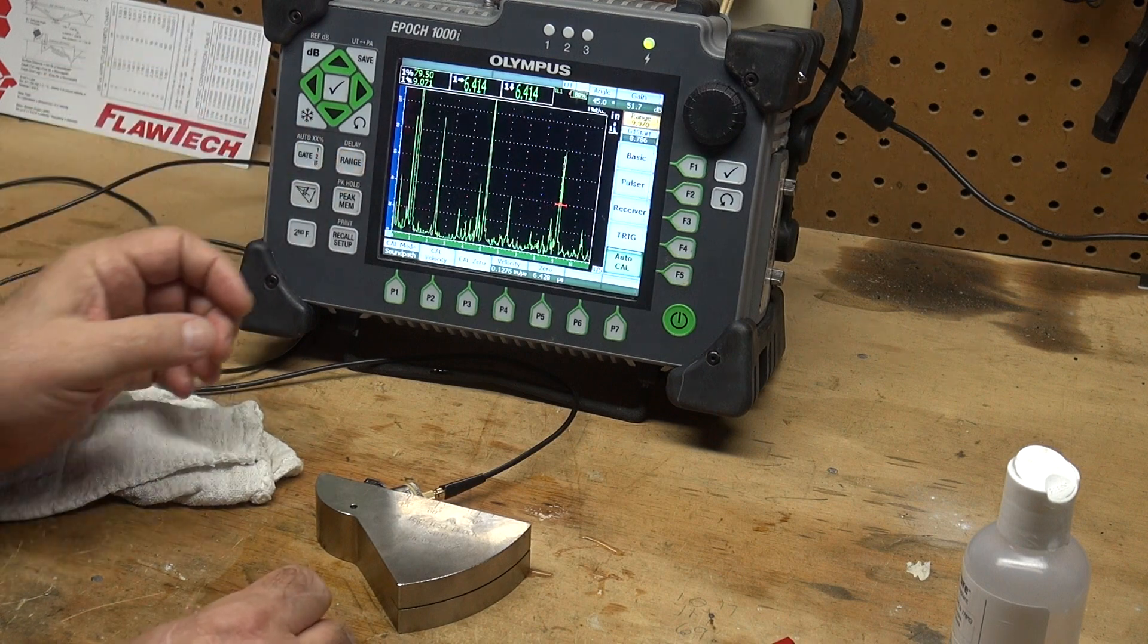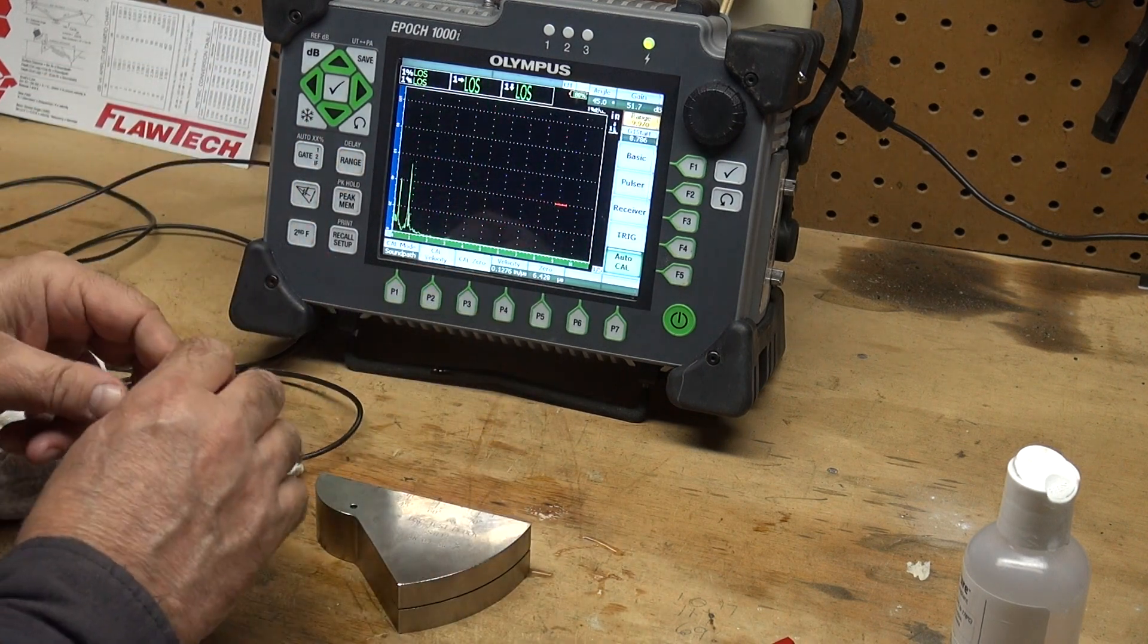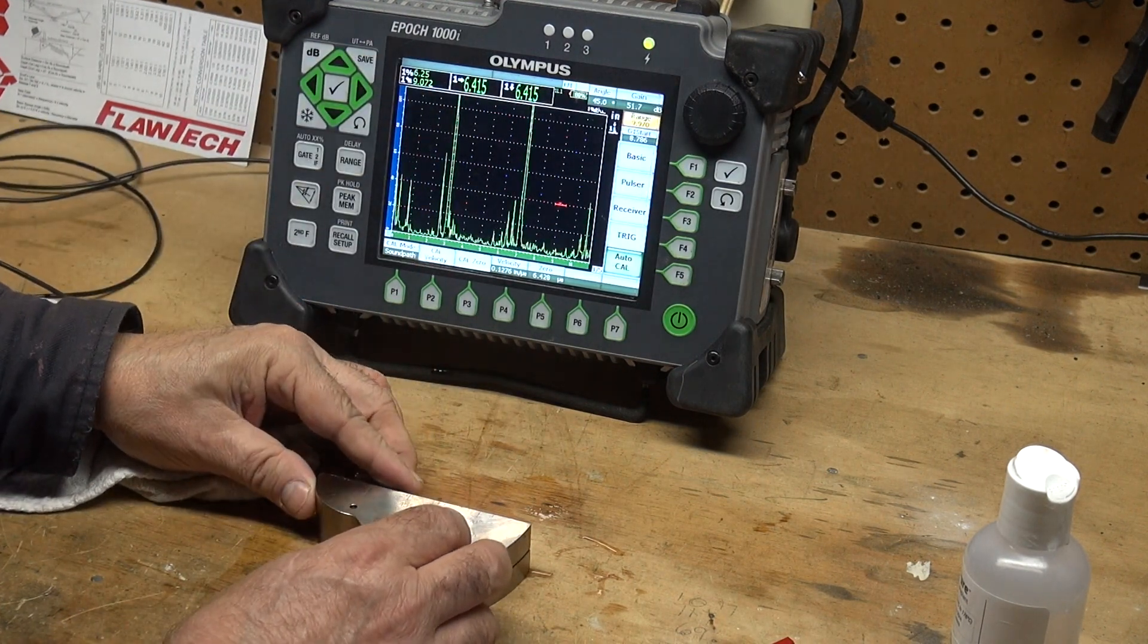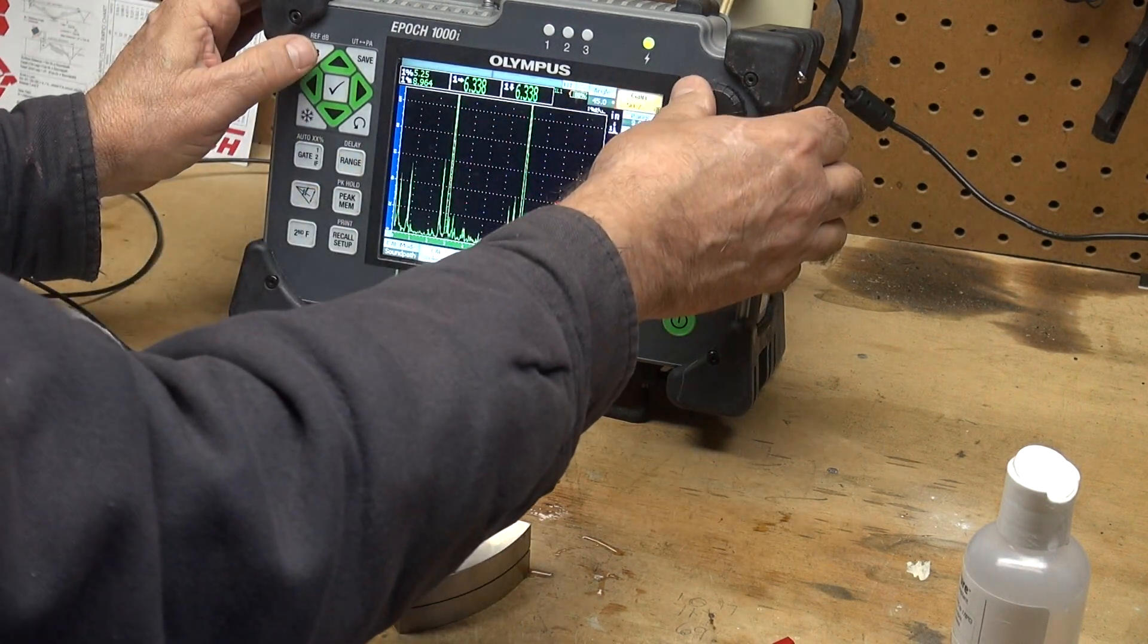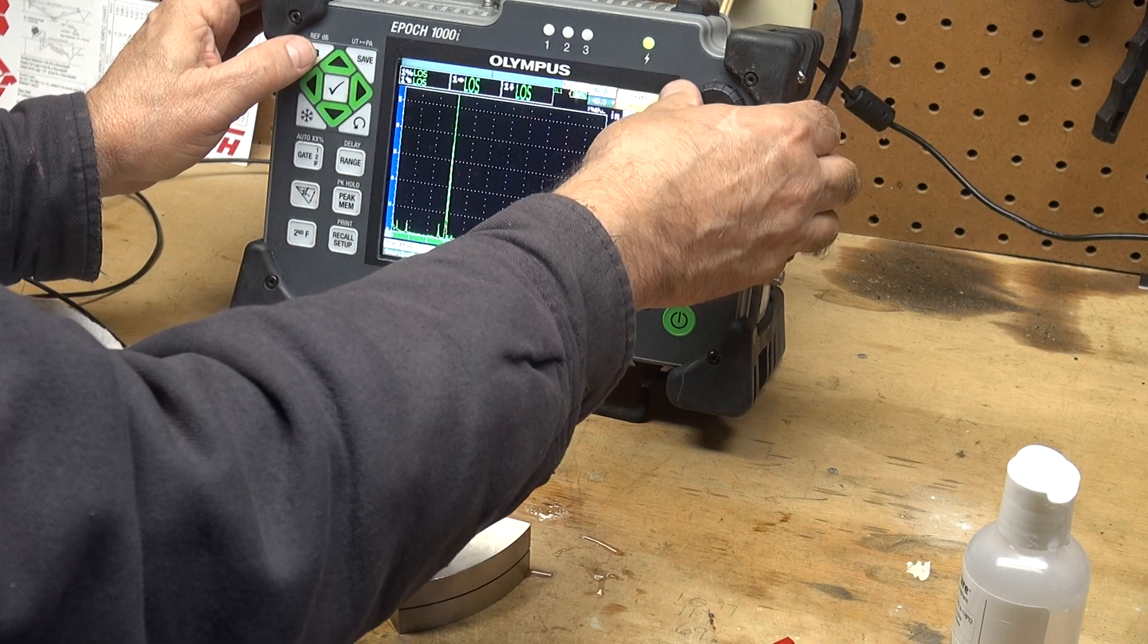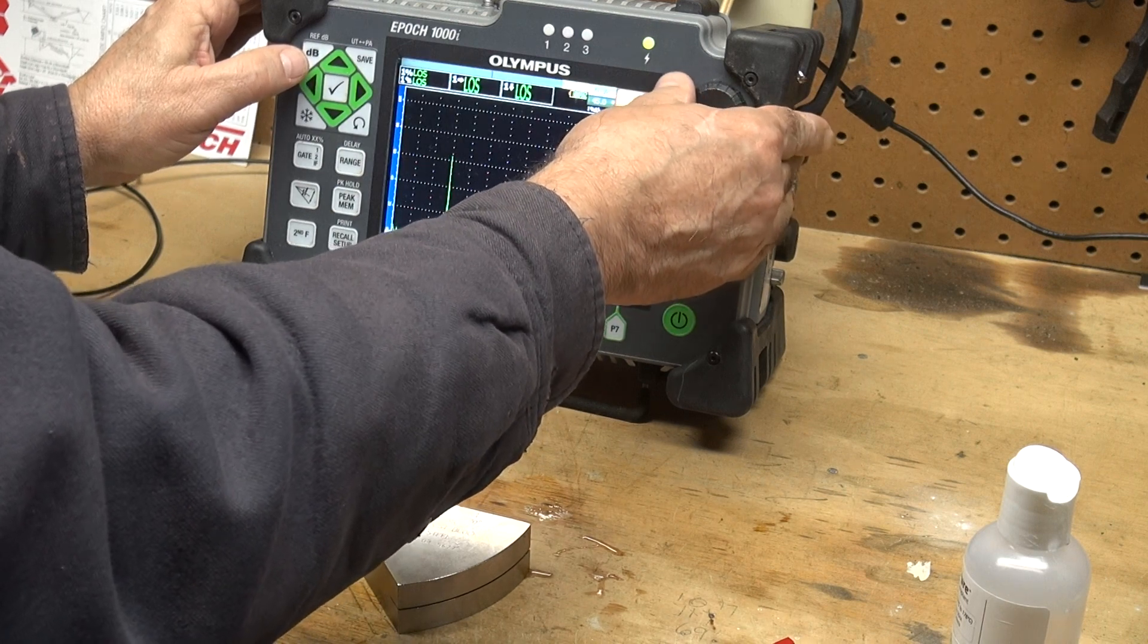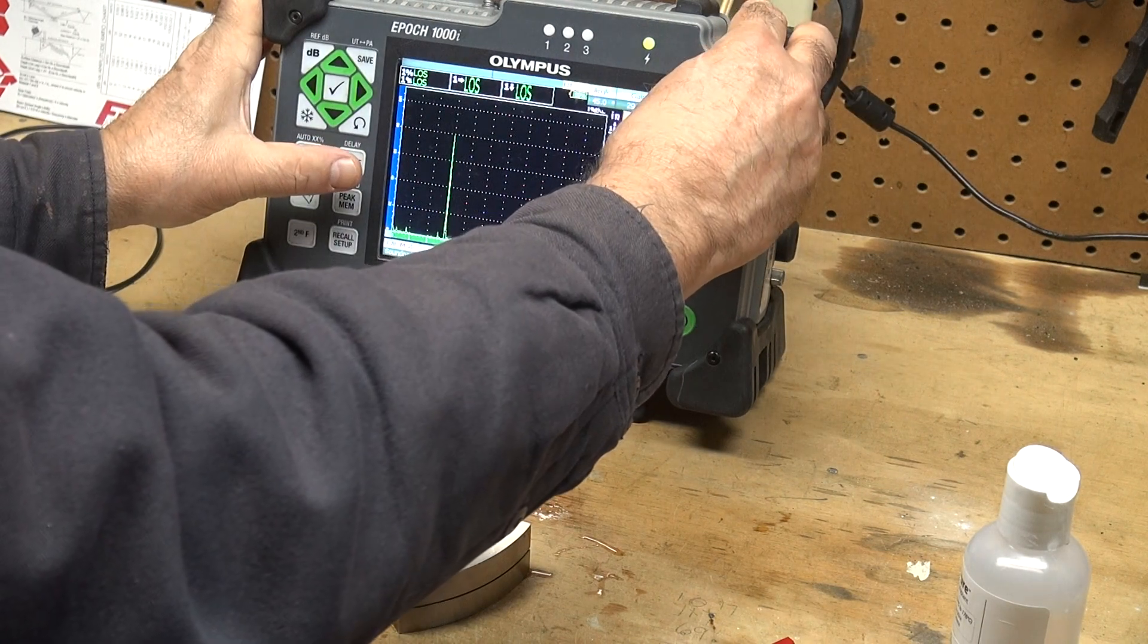Let me show you something else. You can flip this guy around and you can see a three-inch. This transducer zero here, we will see a three-inch, seven-inch, and an 11-inch reflector. Let me change my range to 11 inches.